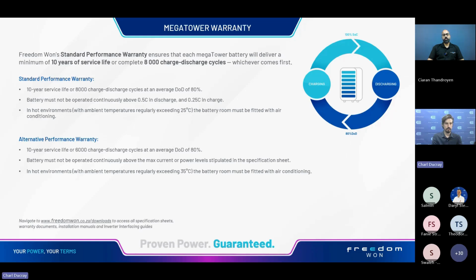With our alternative performance warranty, we basically state the battery must not be operated continuously above the max current or power levels stipulated in the specification sheet. Essentially, it shouldn't be operated past the maximum C rating capability of that particular battery.